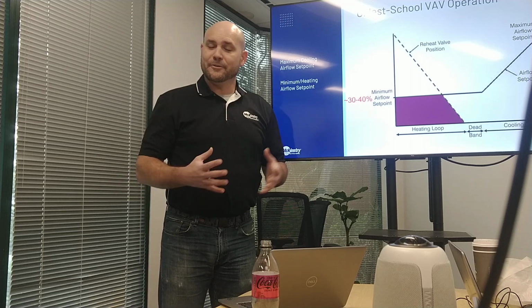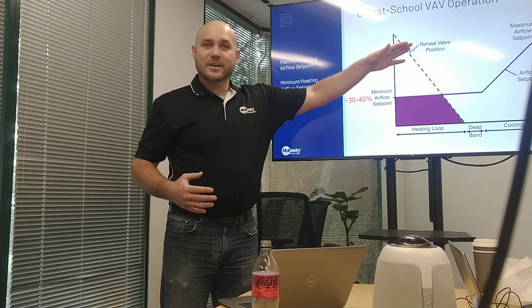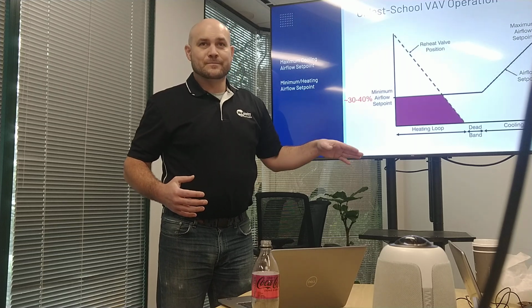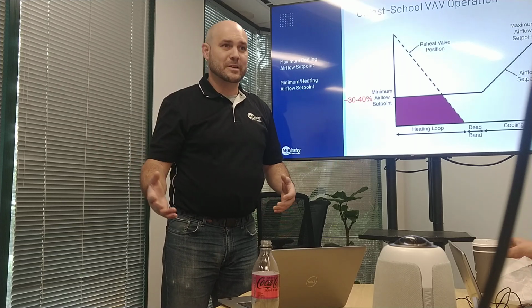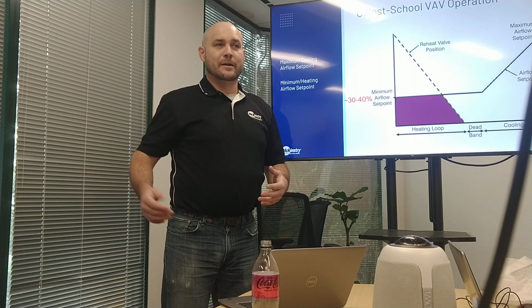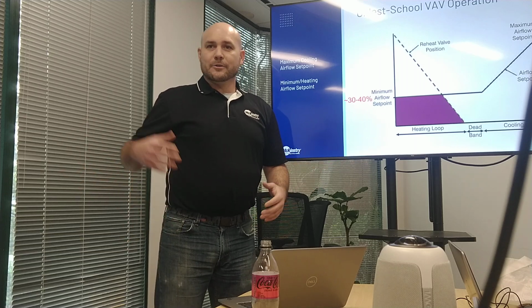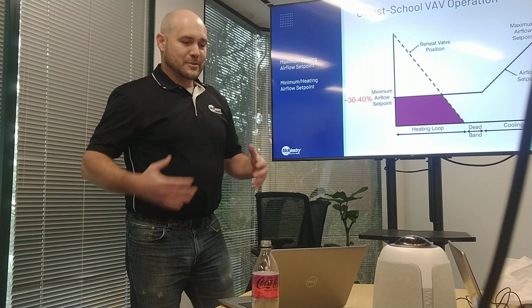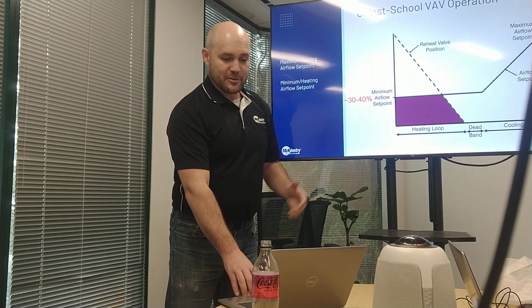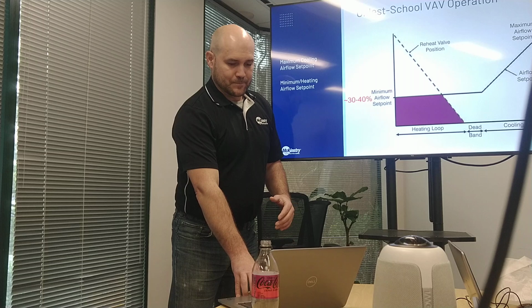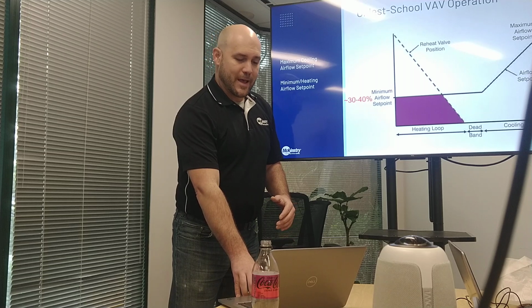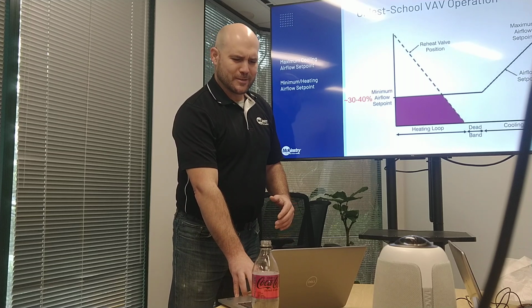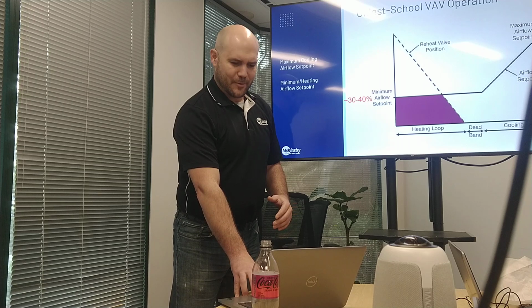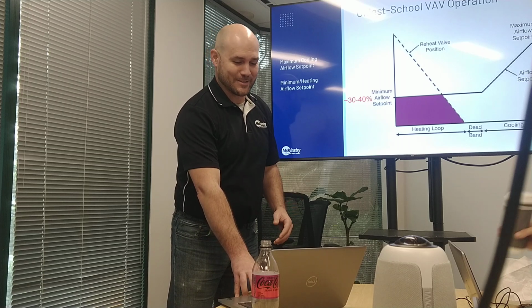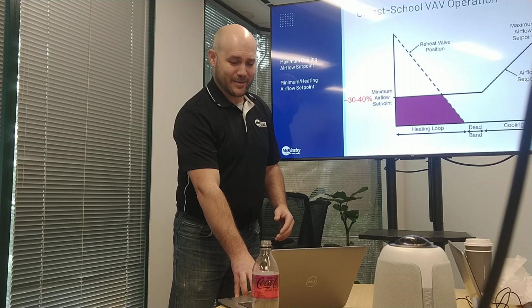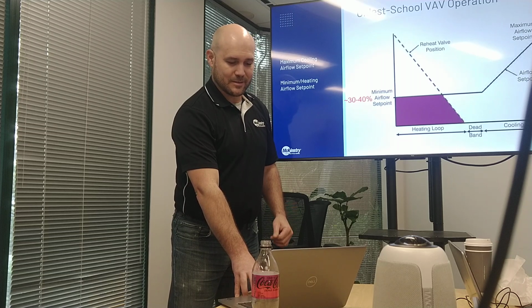You did a lot of calculations to determine the load for what the maximum one should be for heating. Just make sure there's enough BTUs going into the space. It didn't matter if you're supplying 95 degree air or 120 degree air. As long as there's enough heat being supplied into the space, it didn't matter really what the airflow was. Reflect on that. That's really a thoughtless and haphazard approach, but that's how design was done, and I suspect to a large degree still is done.